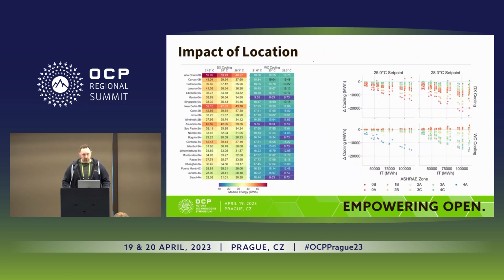This is my favorite chart I've ever made, because it's a direct comparison between direct cooling and pre-chilled cooling. This is the impact of location on data center design and why it cannot be ignored. At the top, we're ranging from the warmest, which is Abu Dhabi, right the way down to what we class as a 4A in Seoul. And it goes lower, down to 8, with Iceland and areas of Denmark within that.